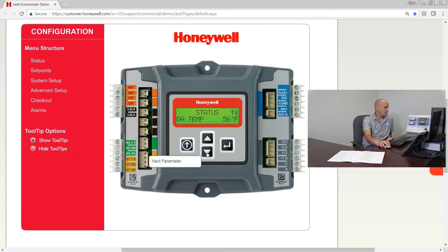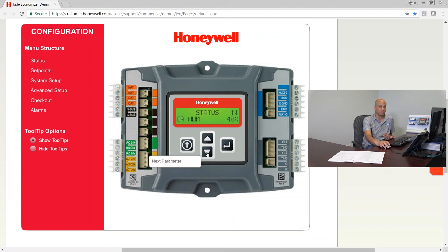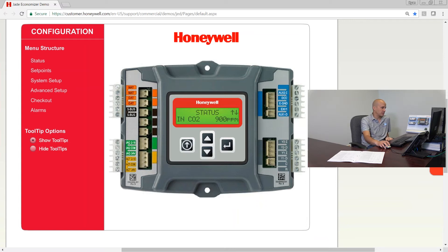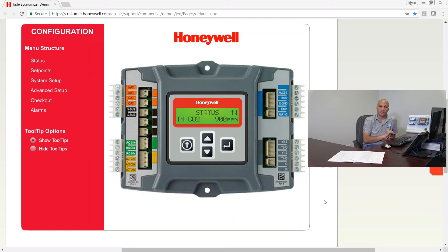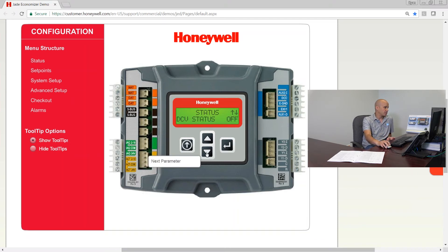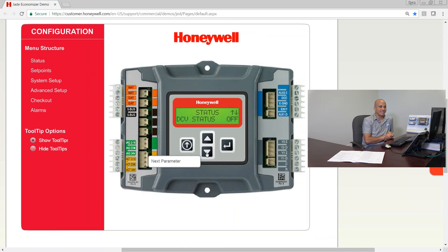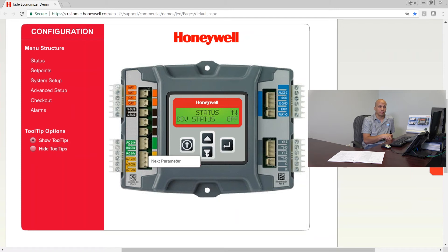Below that group of Y1 ins and outs, I have my mixed air temperature — I can see what that's actually reading right now; ours is reading 53 degrees at the moment. Then there's my discharge air temperature sensor if I have that optional sensor, outdoor air temperature sensor, outdoor air humidity percentage, return air temperature if I have that optional sensor, return air humidity percentage if I have that sensor, and if I have a CO2 sensor, I'll have my input CO2 — right now we're reading 900 parts per million.